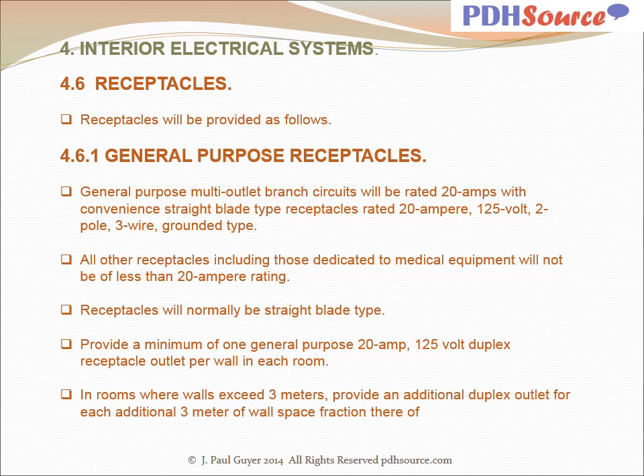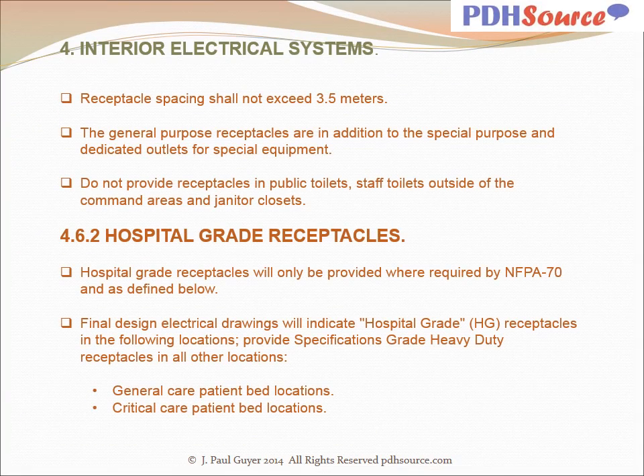Provide a minimum of one general purpose 20 amp 125 volt duplex receptacle outlet per wall in each room. In rooms where walls exceed 3 meters, provide an additional duplex outlet for each additional 3 meters of wall space or fraction thereof. Receptacle spacing shall not exceed 3.5 meters. The general purpose receptacles are in addition to the special purpose and dedicated outlets for special equipment. Do not provide receptacles in public toilets, staff toilets, outside of the command areas, and janitor closets.